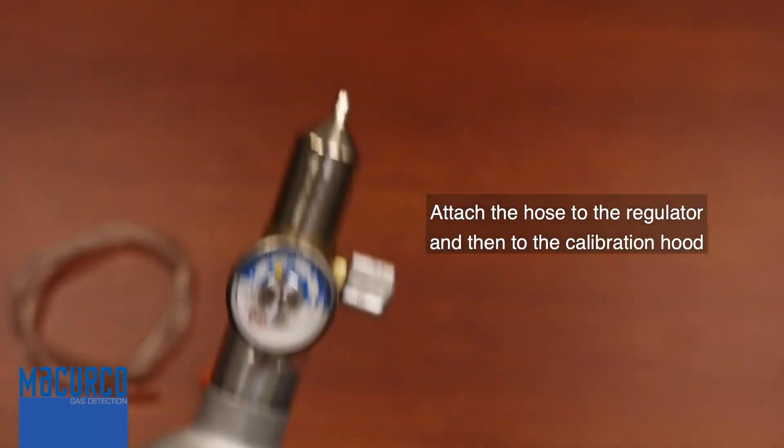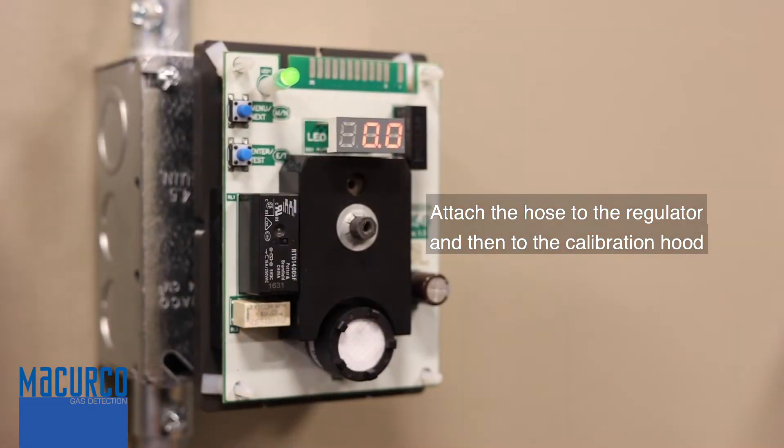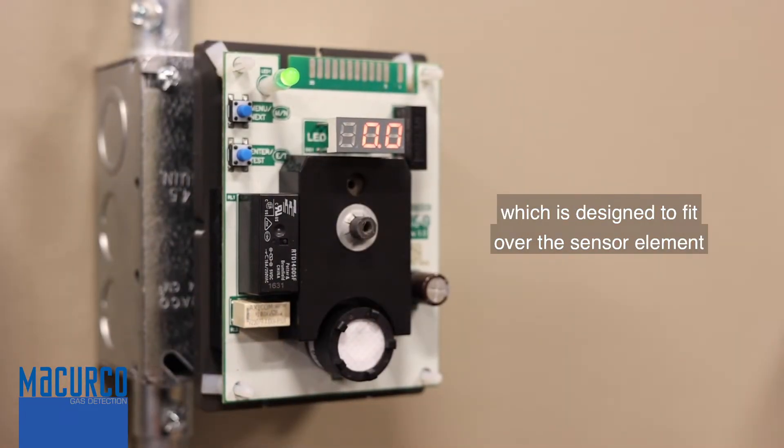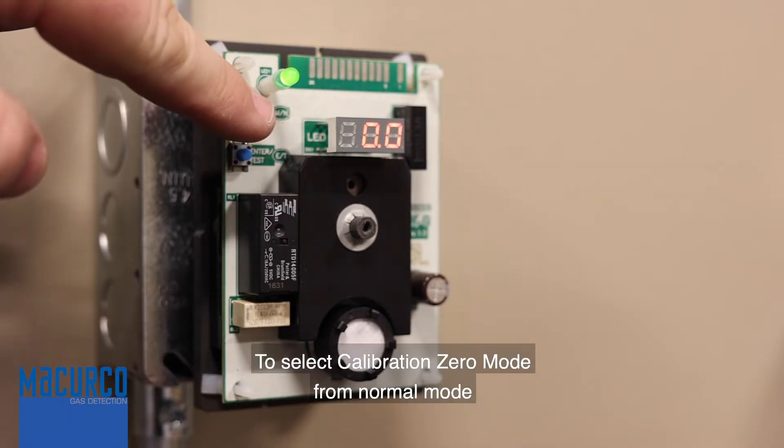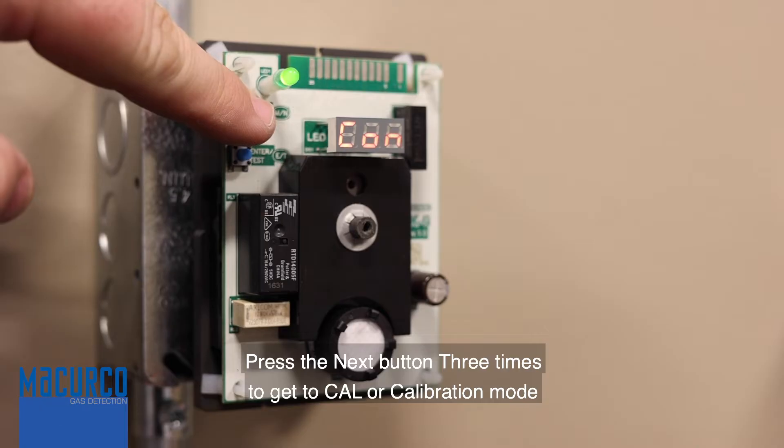Attach the hose to the regulator and then attach the hose to the calibration hood, which is designed to fit over the sensor element. To select calibration zero mode from normal mode, press the next button three times to get to cal or calibration mode.